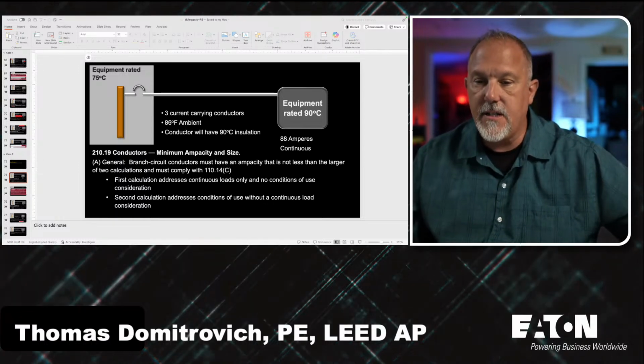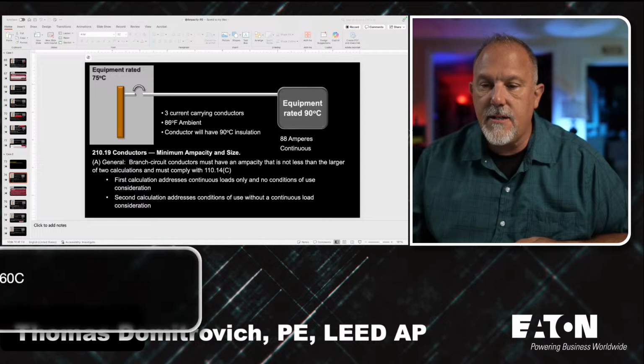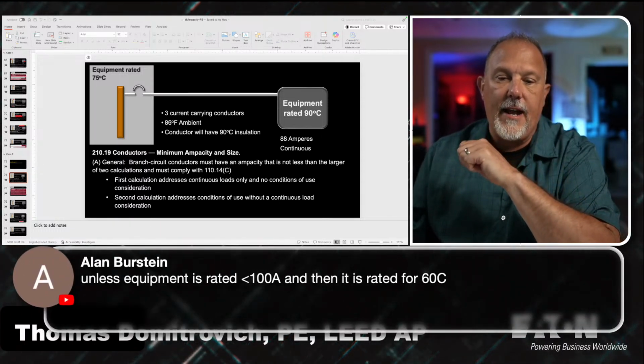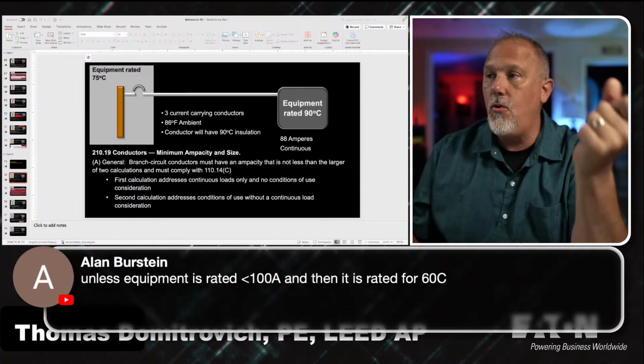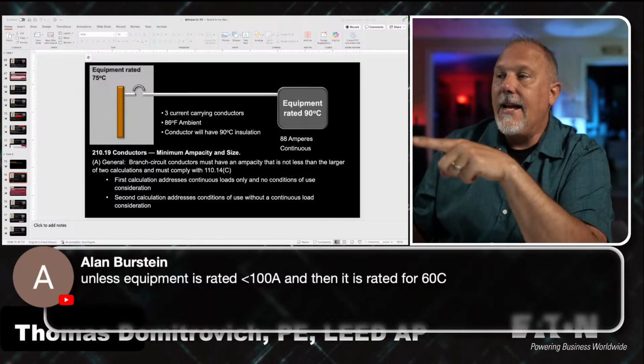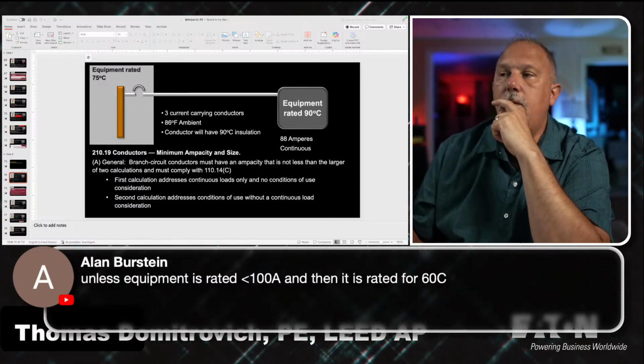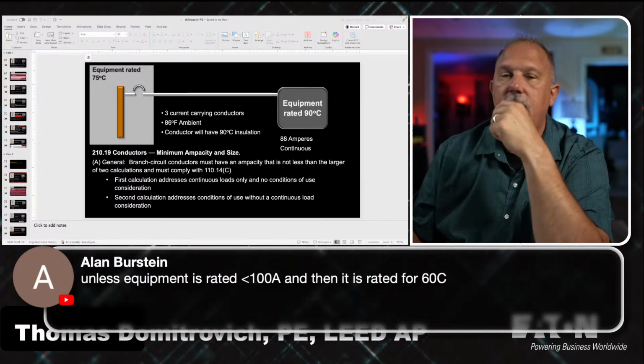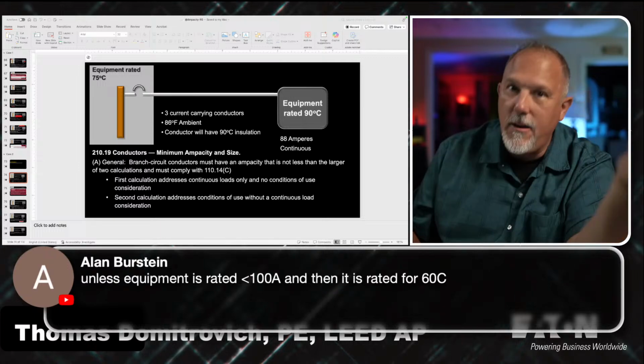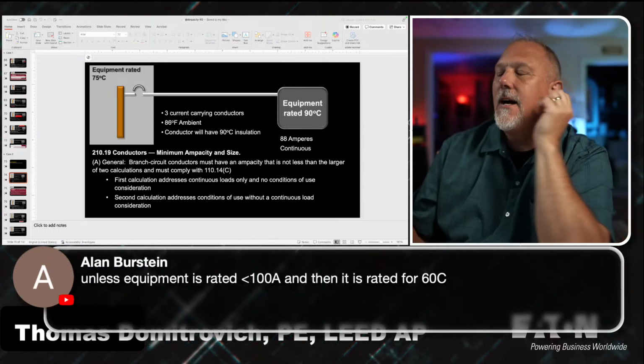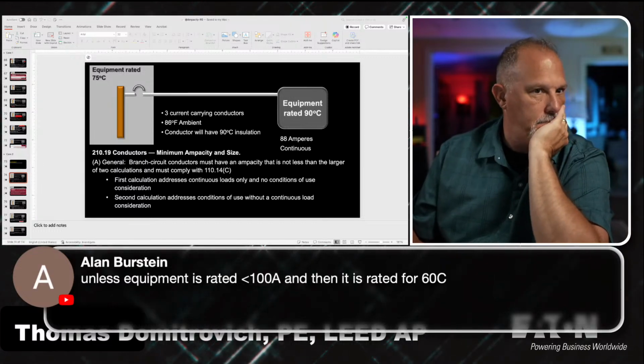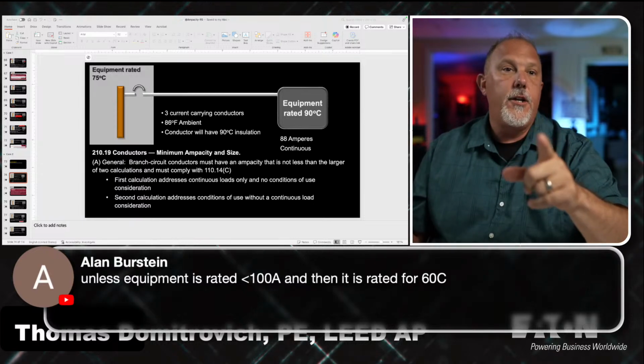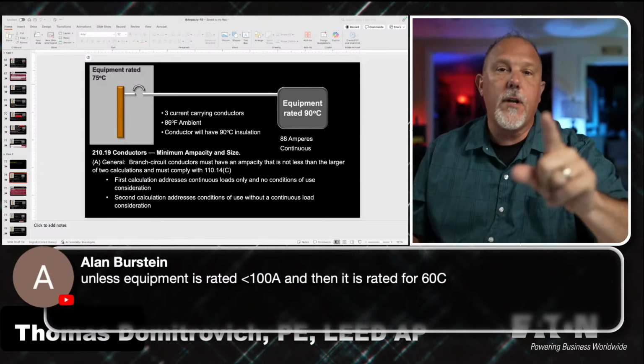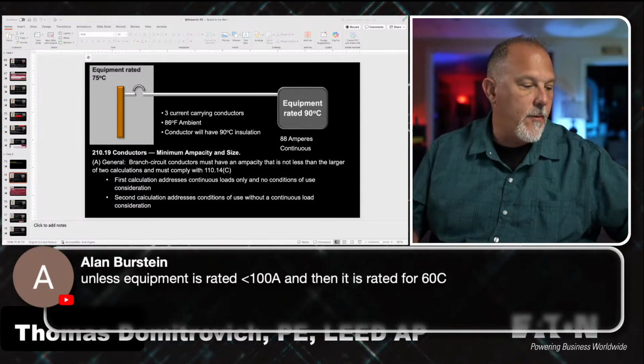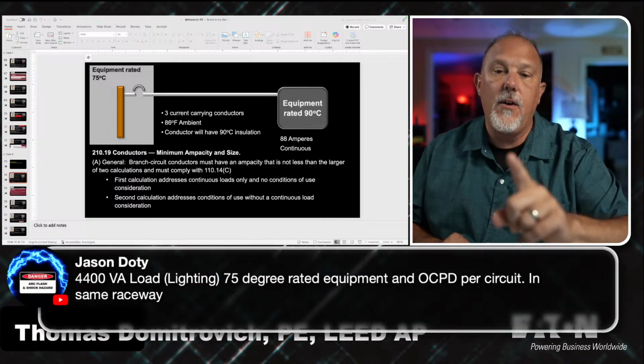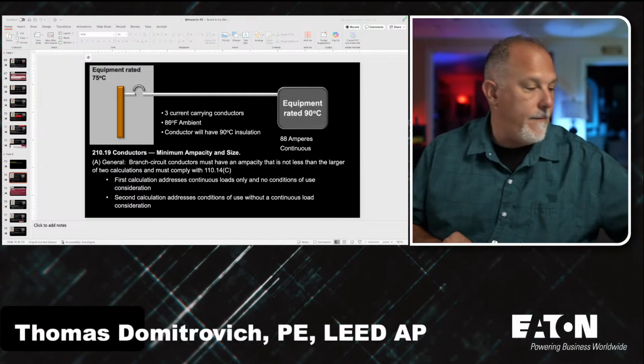Okay? Perfect. Excellent. And then Alan says, unless equipment is rated less than 100 and then it is rated for 60. Ooh, and I've got equipment that's 88 amps continuous. Oh, boy. You know what I like about you, Alan? You know what I don't like about you, Alan? You always are right. You're right. Oh, no. No, wait a second. Hold on, Alan. We're going to get to 110.14. So we're not going to worry about the equipment right now. So let's handle that when we come to it.